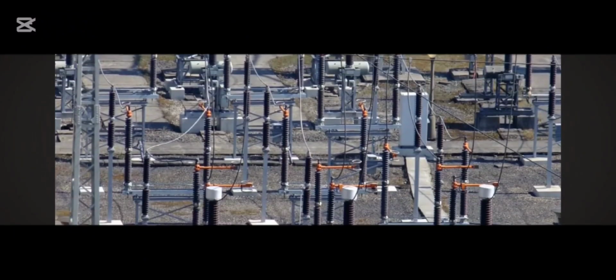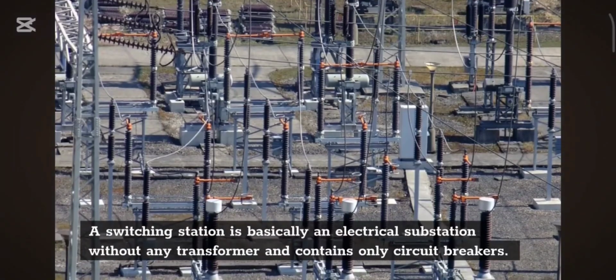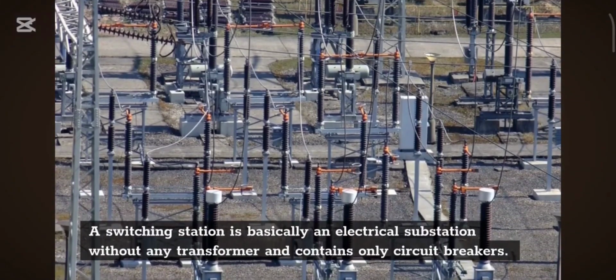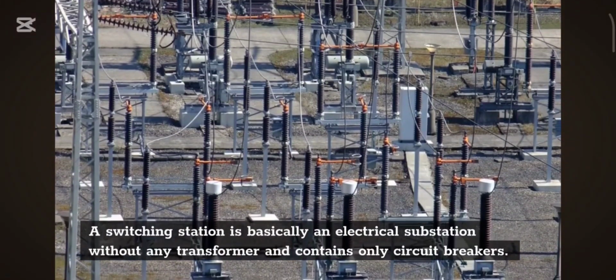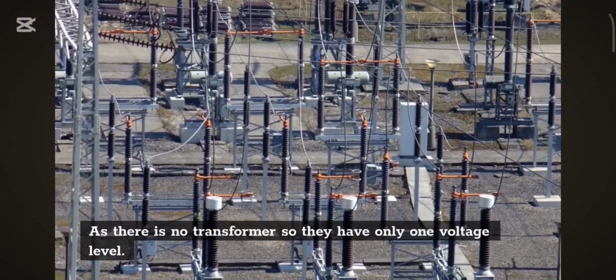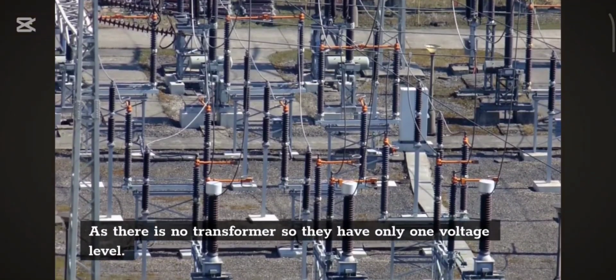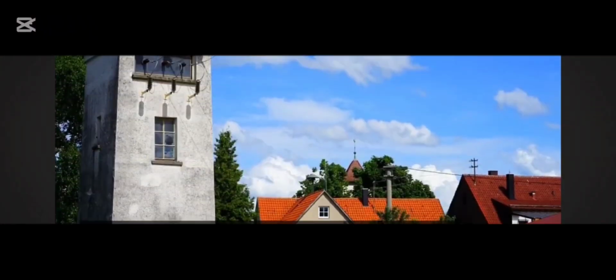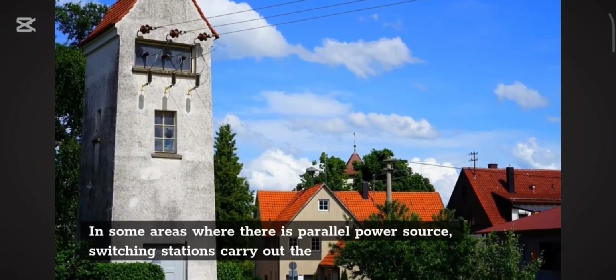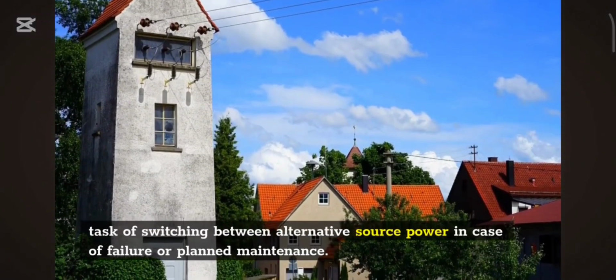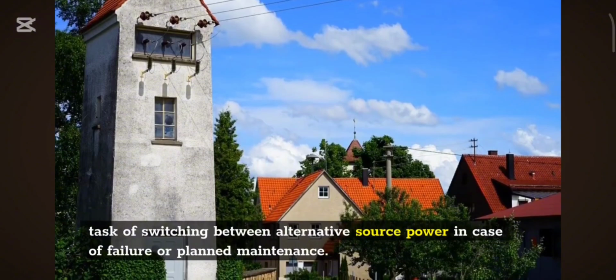Switching station. A switching station is basically an electrical substation without any transformer and contains only circuit breakers. As there is no transformer, they have only one voltage level. In some areas where there is parallel power source, switching stations carry out the task of switching between alternative source power in case of failure or planned maintenance.